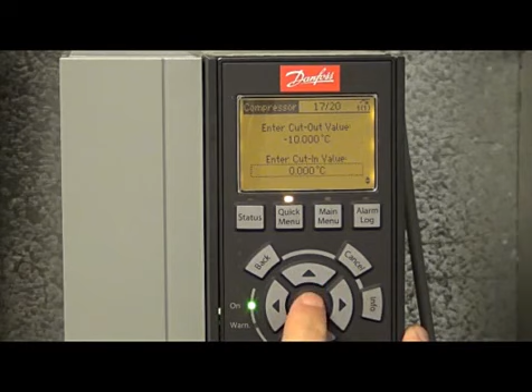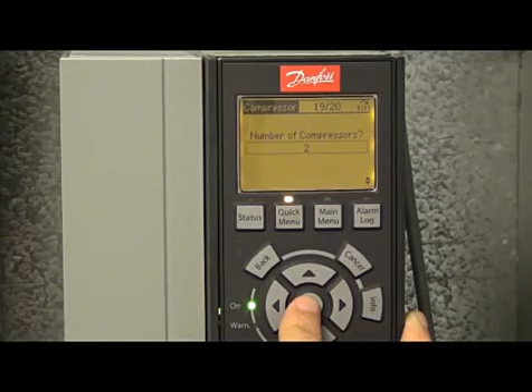Then in this case we do have 2 compressors in the system. This is what pack control means, that you can control up to 3 compressors. You're now asked, do you have more than 1 compressor, or do you wish to configure pack control? We'll say yes to that. Okay. Arrow down. How many compressors do you have? We have 1 variable speed and 1 fixed speed, so 2 compressors it is.